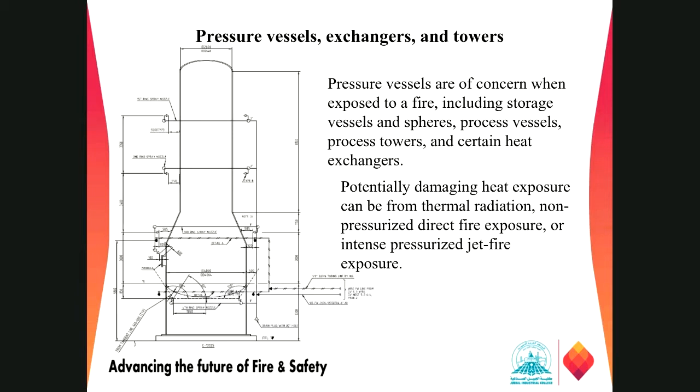And then we have a pressure vessel site. For the pressure vessels also we need a water spray system. If you can see, we have different rings. This is ring 1 at the top, this is ring 2 at the middle, and we have a ring at the bottom there, right? We have 3 rings, and then we have a detection line to detect the fire, right?